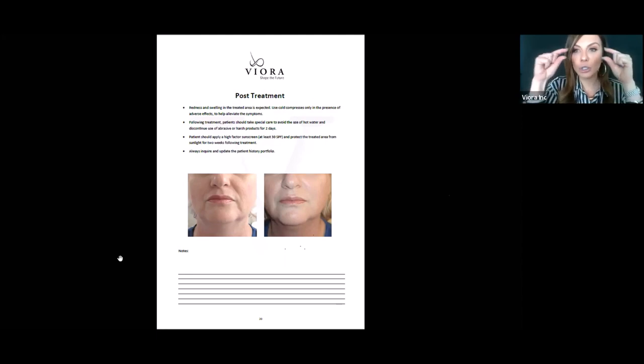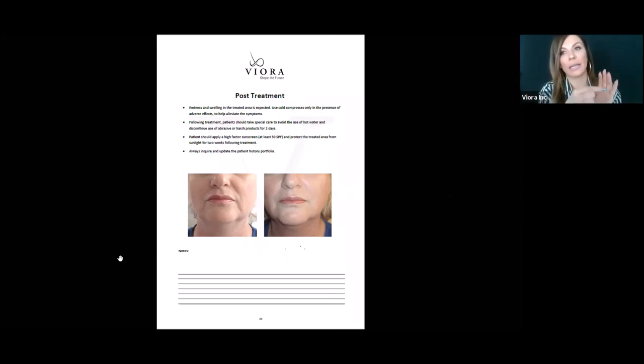Now you have two little tips per handpiece, and you'll only use one tip for half the life of the handpiece. Then it starts to get kind of compromised because of the glycerin, and it can pop off when it's not supposed to. That's when the second tip would be placed. So it's about 3,000 minutes with the first tip. When you get to about 3,000 minutes, or it starts to not clip on and hold onto the handpiece well, then that one is no longer needed. You can go into your box and get your new tip and use it for the rest of the time.